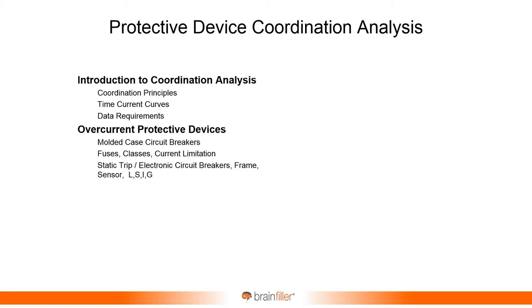We're going to look at static trip or electronic trip circuit breakers that have what's known as a long time, short time, instantaneous, and ground function — often called LSIG. We'll also look at ground fault protection separate from those LSIG electronic or solid state breakers.